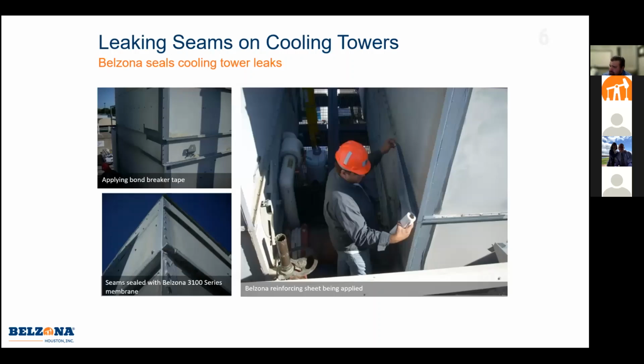A lot of times you get leaks on the towers on the external seams where, especially in these summer months, it's almost impossible to shut down the cooling tower, take out all your fill, and drain your towers just to get in there and repair these seams. We have options where we can take our 3100 series or flexible membranes and basically seal the seams from the outside, and that's what we're doing here. It's a low prep scenario - a lot of times really just some sandpaper and wire brushes will help with this certain series. But if you want us to go the full route of abrasive blasting, etc., we can do that as well. It just depends on what you want.